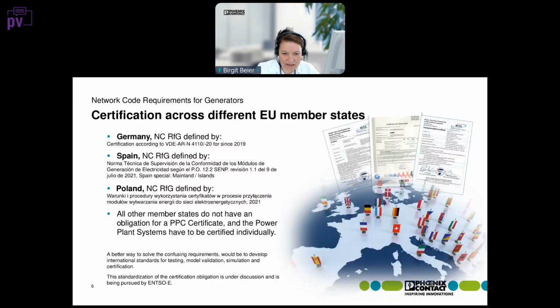But let's look at the next slide. Not everywhere does the PPC have to be certified. To be exact, only in 3 countries is there an obligation for certification. Those 3 countries are Germany since 2019, where certification has to be done according to the VDE-AR-N 4110/4120. Then there's Spain since last year, and it's all defined in the NTS. There's a specialty for Spain because there's a difference between mainland Spain and the islands: the islands are not connected to the mainland grid, and therefore there are higher demands for stability. And then we have Poland since last year as well, and it's all defined in warunki i procedury and so on.